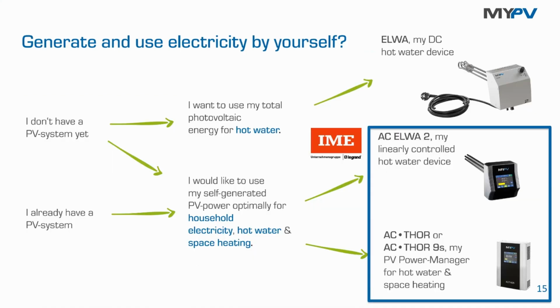All right. So there are 2 solutions from MyPV that can receive the meter signal from an IME meter. To be complete, this is our ELWA solution. It's the only DC solution we have. And if you're interested in a solution like this, you can directly connect your PV panels to this immersion heater. There is no inverter in between, and now you're really autonomous. So it also works during grid blackouts, and you do not even need a permission from the grid operator. So enough on ELWA.